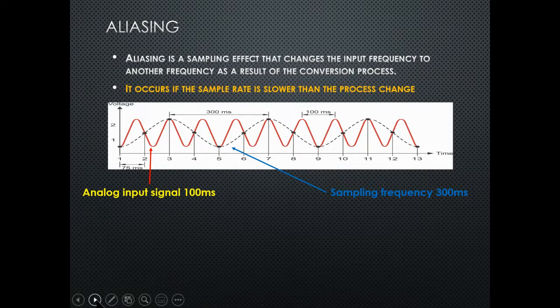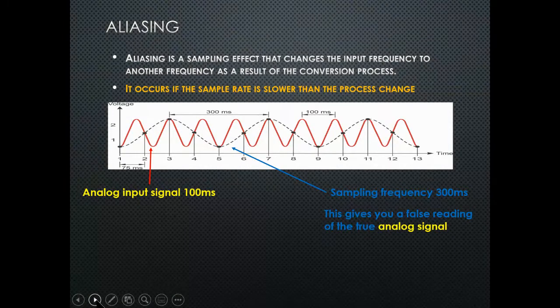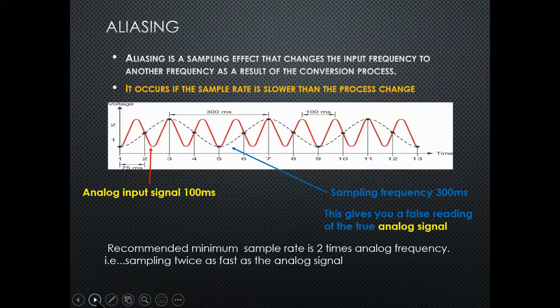If the sample rate is slower than the process change, you get a lot of error — a false reading of the true analog signal. If your analog signal is at 100 milliseconds and you're scanning at 300 milliseconds, that gives a false reading. The recommended minimum sample rate is two times the analog frequency. If the analog frequency is 150 ms, you need to sample at least every 75 ms.